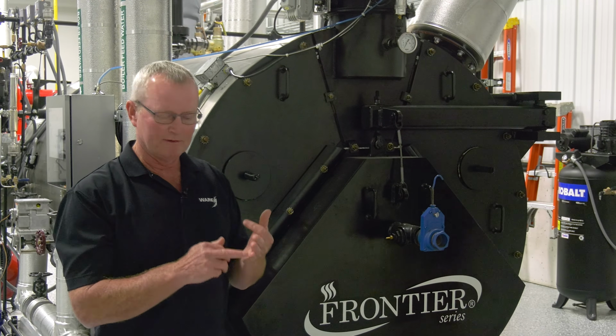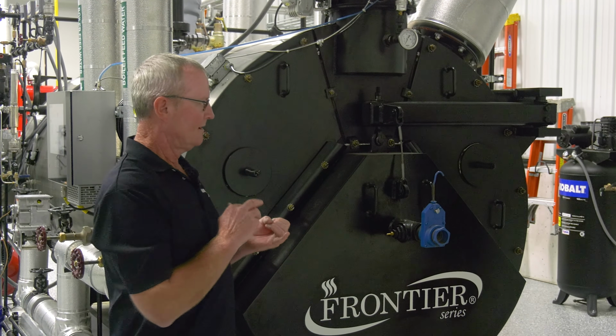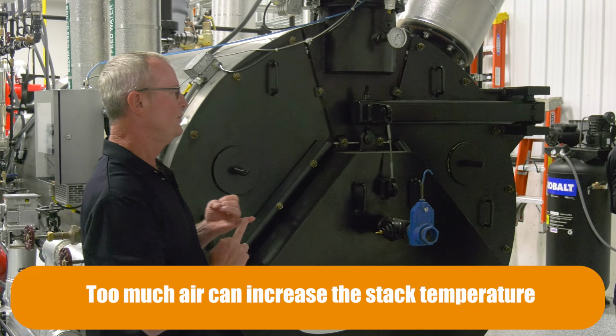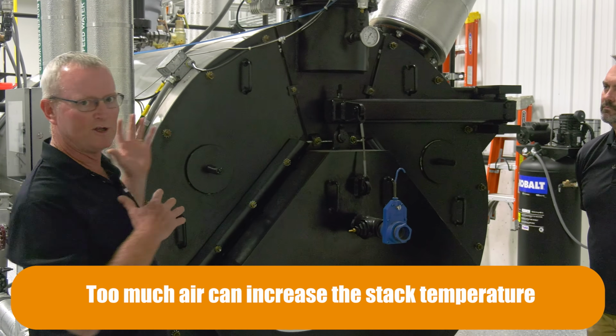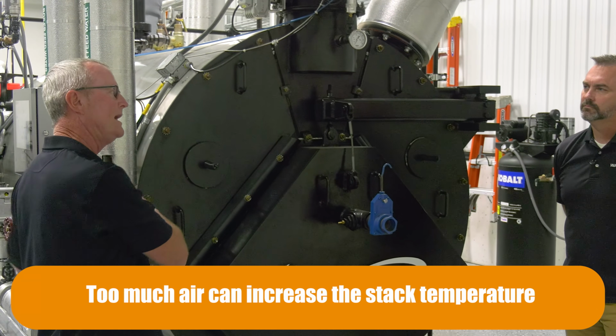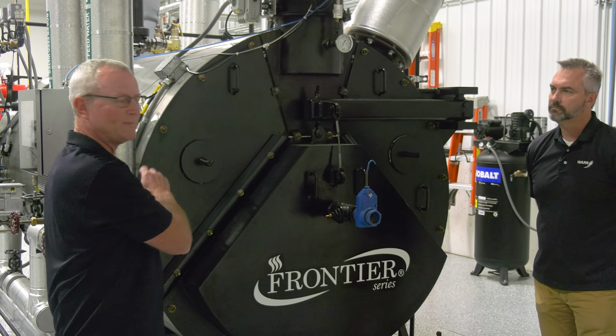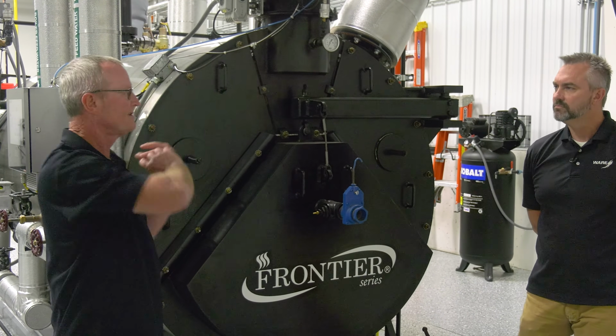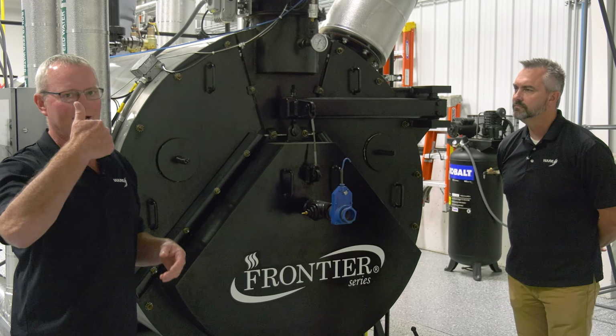There's 3 ways to increase your stack temperature. Too much air. If your O2s are real high, that means you've got way too much air volume going through, so you're taking unburnt gases and just, with the velocity, you're just shoving them right out the stack. Okay. That's going to jack your stack temperature up.